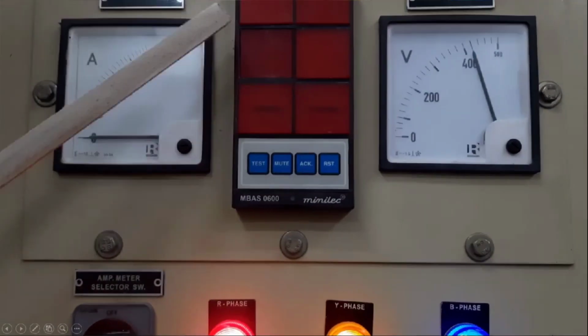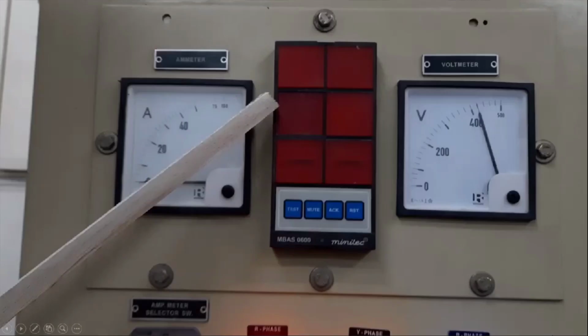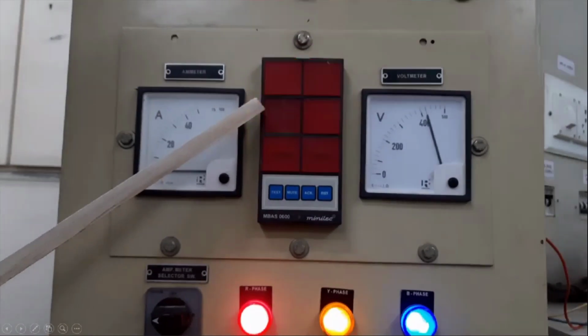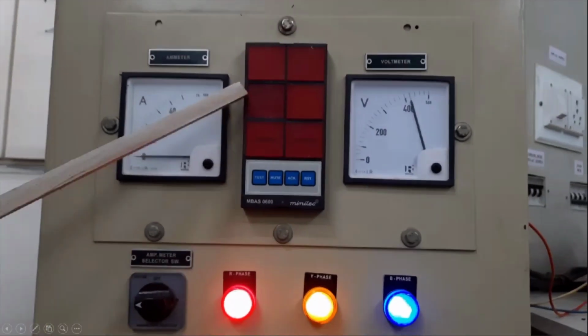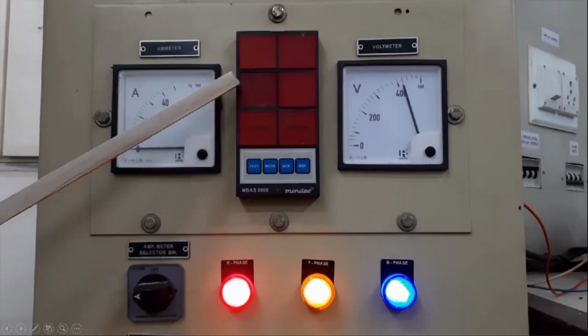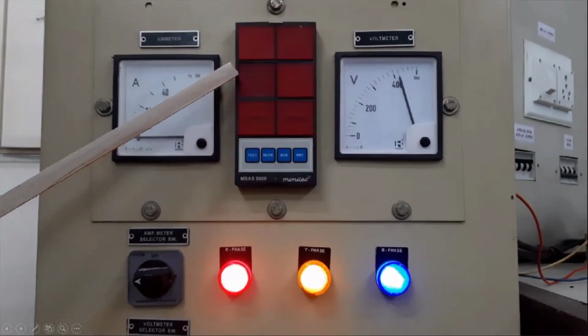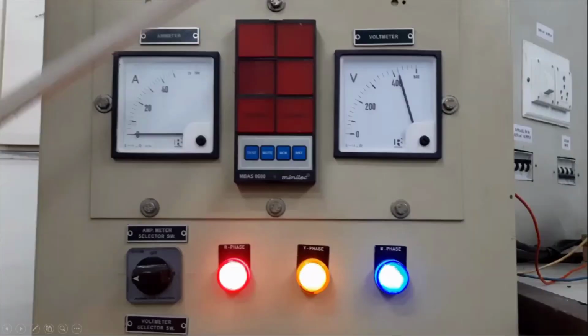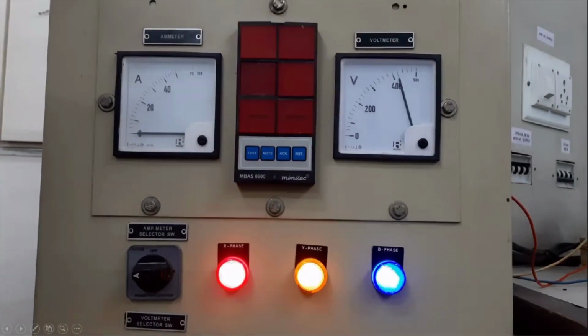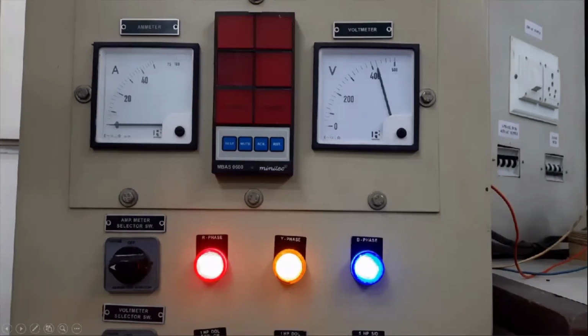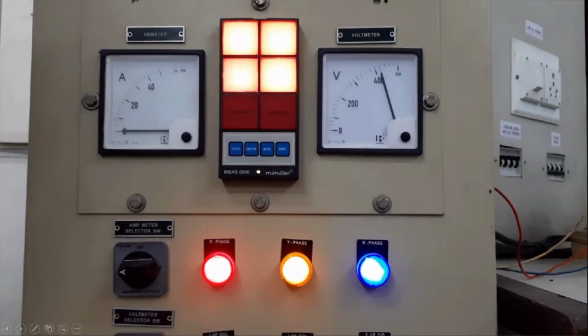Ideally, with annunciator, there is a siren also, because we need to protect the lives of human. So in that condition, in case of a fault and if there are chances of any human fatality or injury, all the operators who are working with the motor should get alerted. So that is why there is a siren along with the annunciator, but since this is for a laboratory purpose setup, we have not kept the hooter.